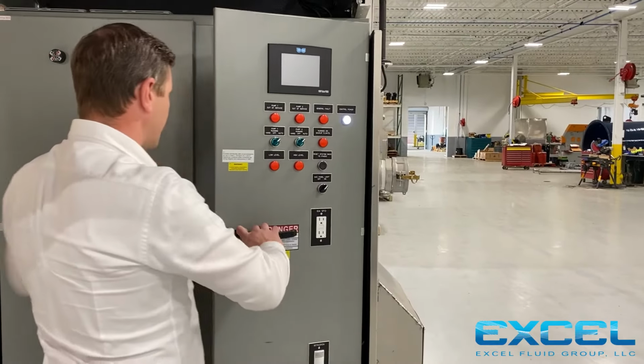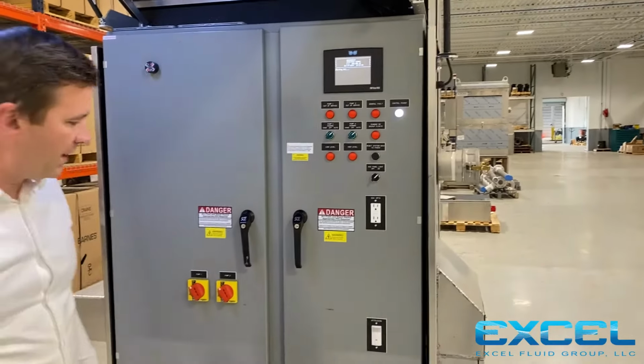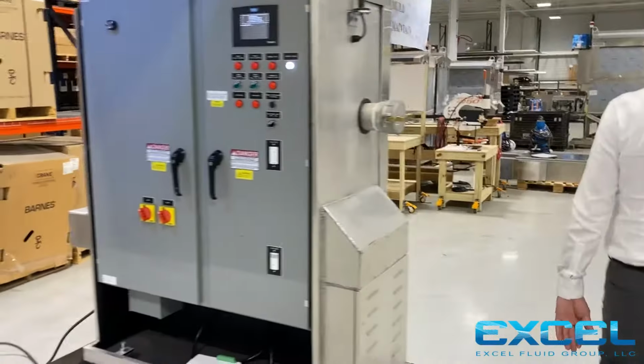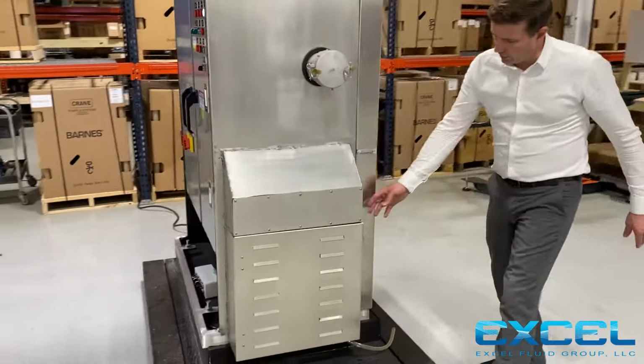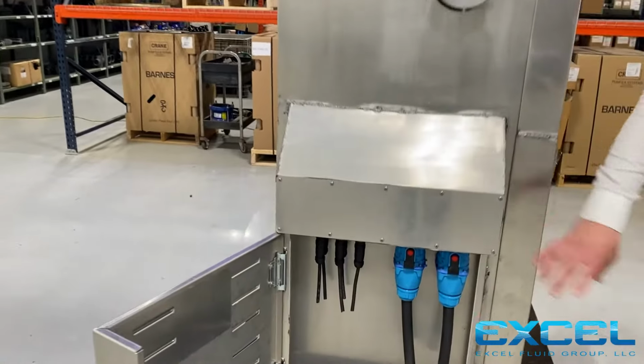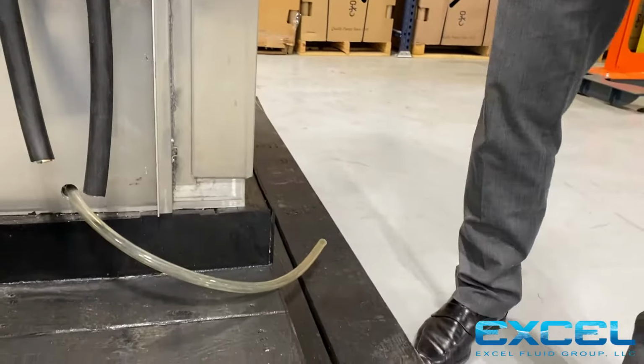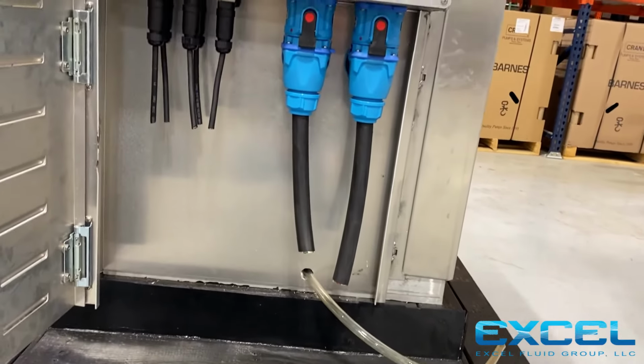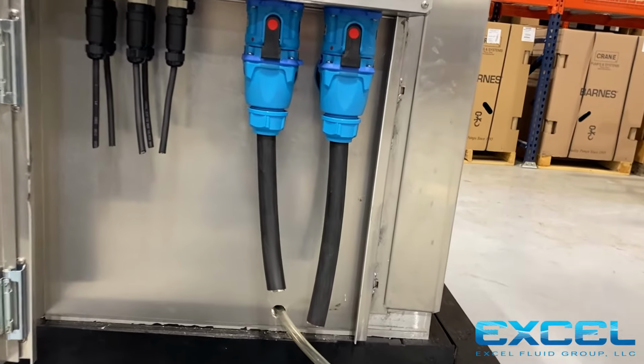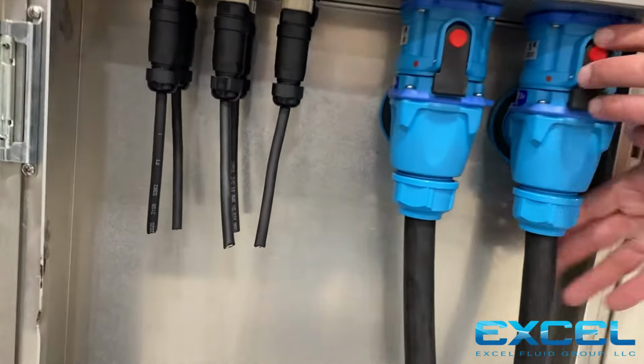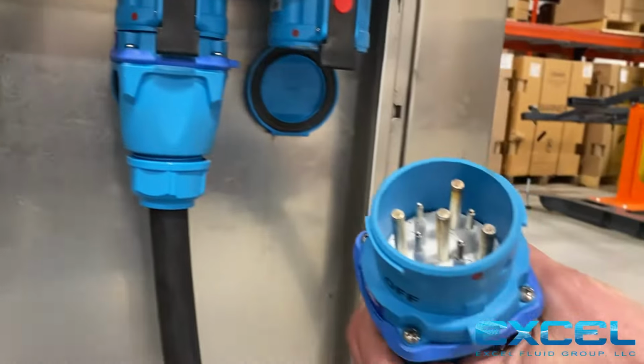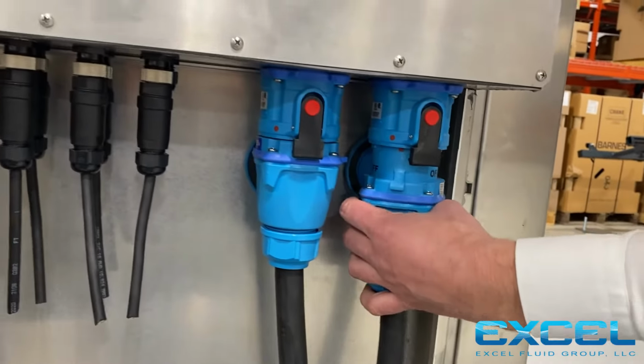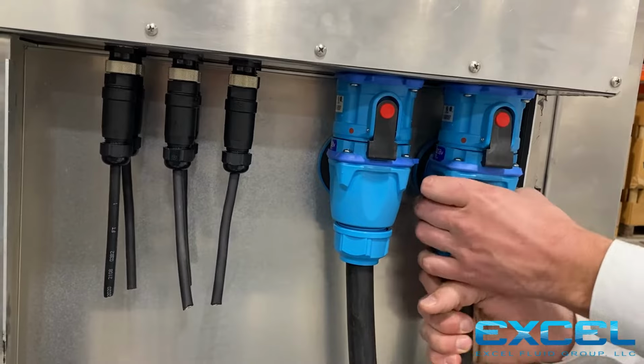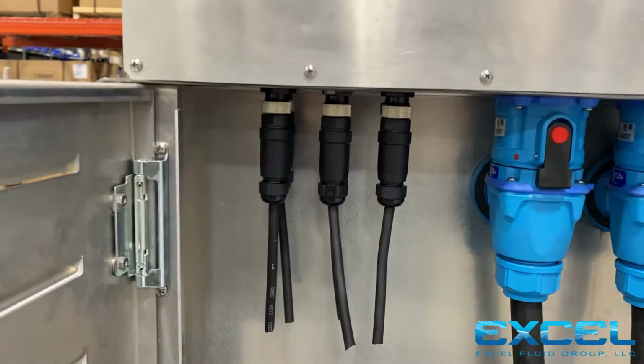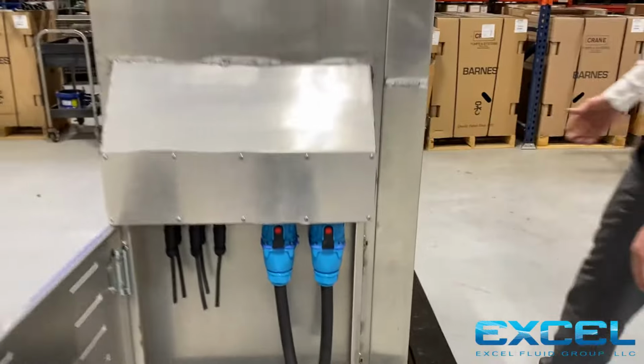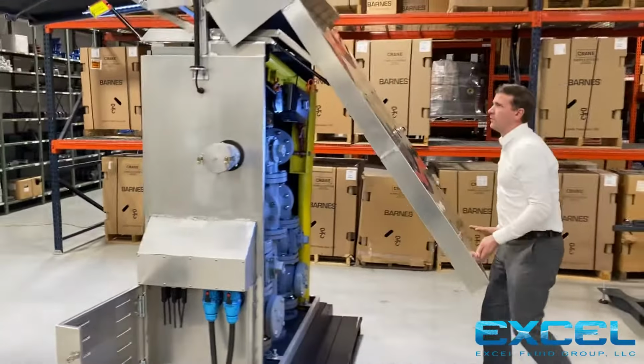Once again, we'll bring on the demonstration power again. And let's go around to the piping side of the wet well. First, we'll take a look at our plugs and receptacles. We're on a cable tray right now that goes into the wet well. If you need to pull a pump for maintenance, it's as simple as unplugging it, pulling out of the cable tray, lifting your pump out, taking it away. There's no conduit, no field wiring. The Meltric plugs are very simple and easy to take off, and that pump's coming with you for replacement or maintenance, whatever needs to happen. Floats plug in here, and we'll come around and take a look at the piping side of the NoVault enclosure.